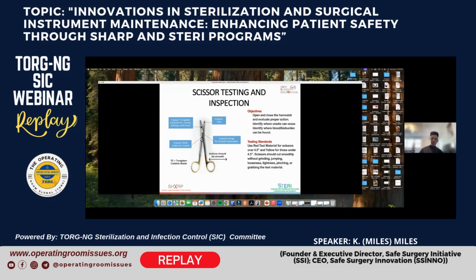It doesn't really matter the type of scissor that you're looking at, because the inspection points are going to be general, based off the functionality of the instrument. So just for starters, we always want to make sure that we're looking at the distal tip of the instrument. That's going to be the tips where the blades meet. So we want to inspect those tips to make sure that they're meeting properly. We want to inspect the blades on the inside for cracks or bioburden.